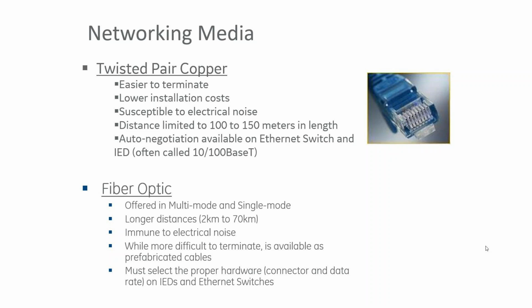Fiber optic's advantage is that it can go very long distances, and it's immune to electrical noise or interference within your facility. So we usually recommend fiber optic for Ethernet networks in industrial or utility environments, which are very noisy EMC areas, so you want your data connection to be immune to that. But for shorter distances, it's easier to use RJ45, making sure to use shielded cables. The disadvantage of fiber optic is that it's more difficult to terminate and splice, requiring special equipment and skill set, and you need special fiber optic media ports on your devices, relays, and switches, instead of electrical ports.